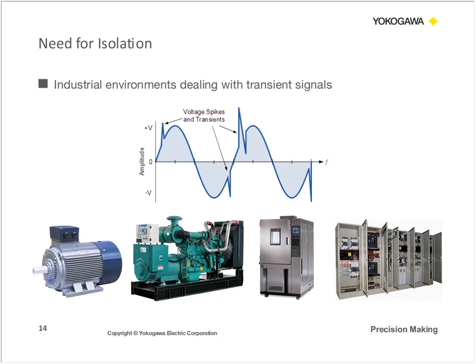So our next situation, obviously, if you're working in an industrial environment where transient signals are common, these are common events or maybe uncommon events, but if there's a potential for those lightning strikes or those short circuits, if you need to implement circuit breakers into your system, you should also consider external isolation as a means or a solution to preventing damage from your equipment. And the external isolation will also protect your data acquisition system from being damaged, as well as ensuring that the measurements you make are correct and not offset by some voltage.